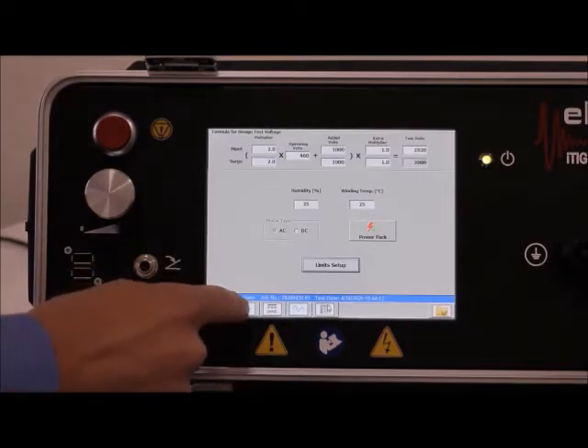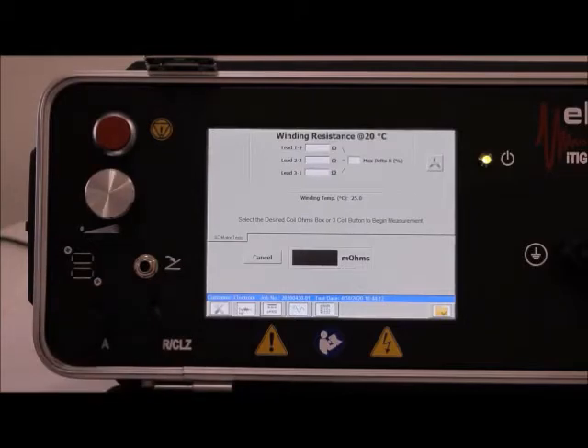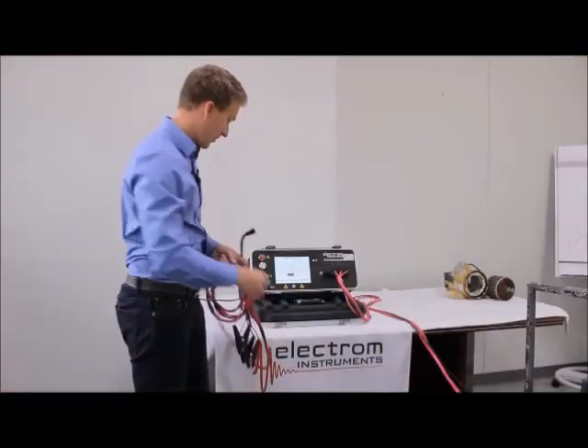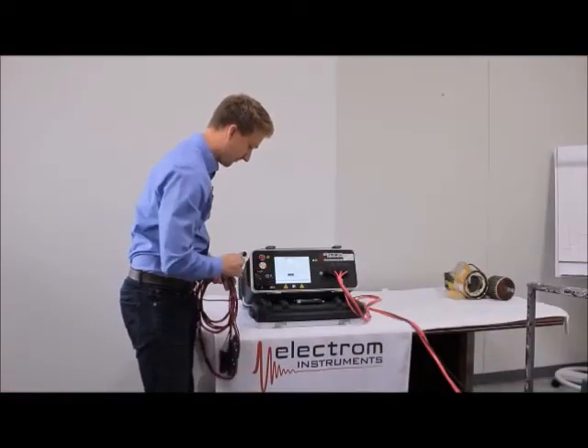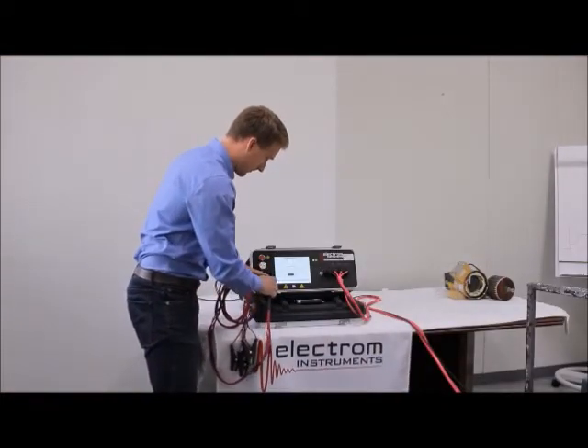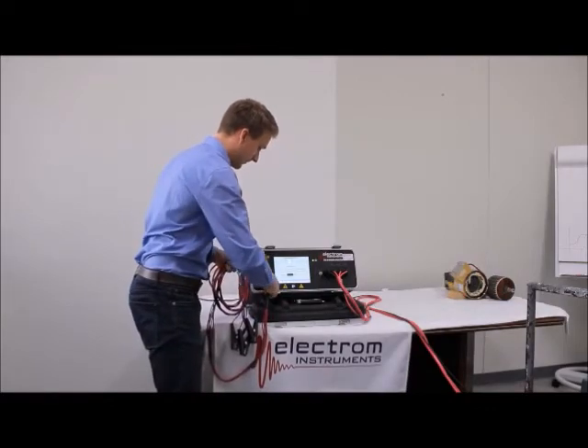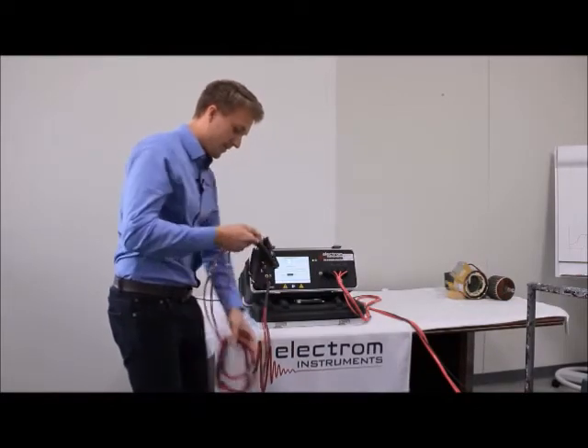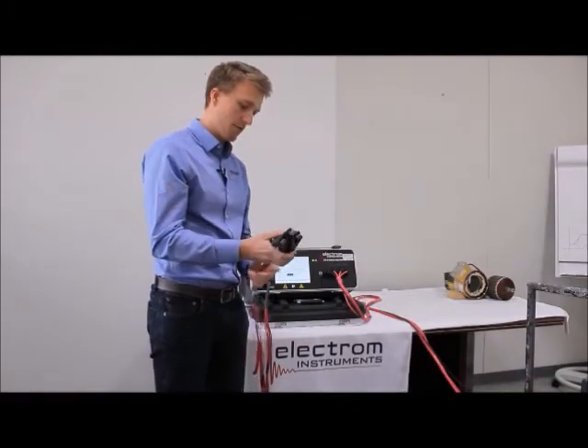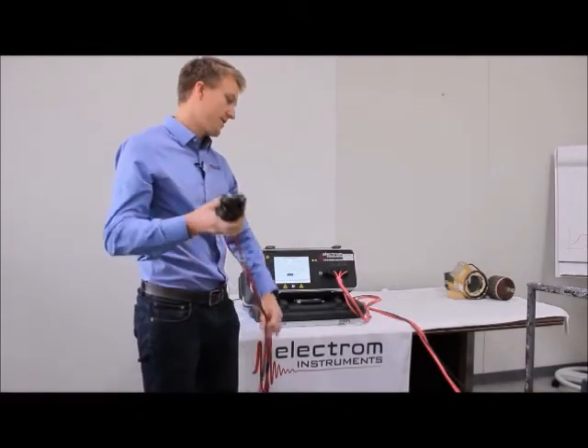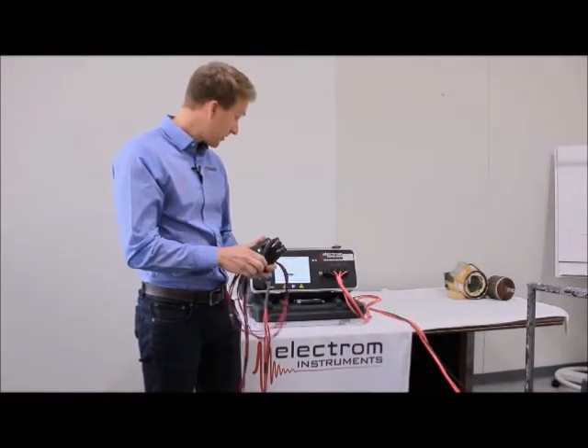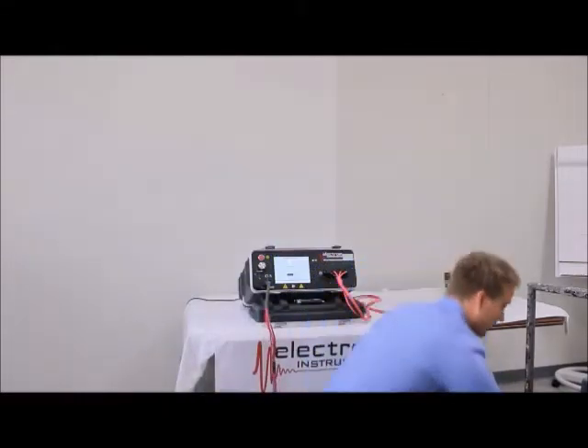So first step is the winding resistance measurement. With the B model, we do the winding resistance with a separate low voltage lead set. Plugs in on the RCLC port here, like so. Three leads, 1, 2, 3, clearly marked and labeled. It's a Kelvin bridge style measurement. We connect to the motor over here.